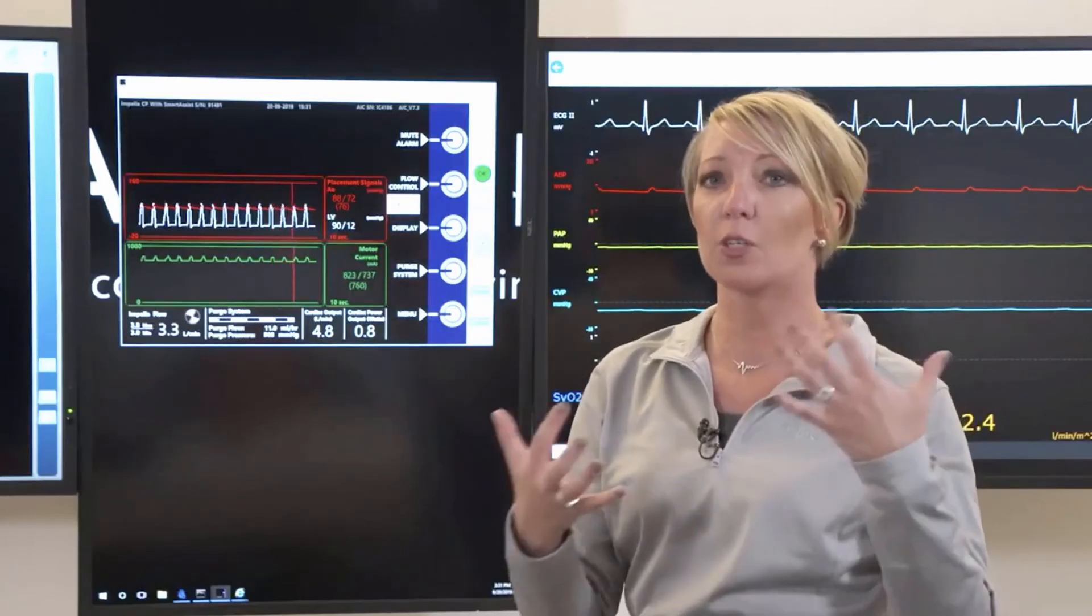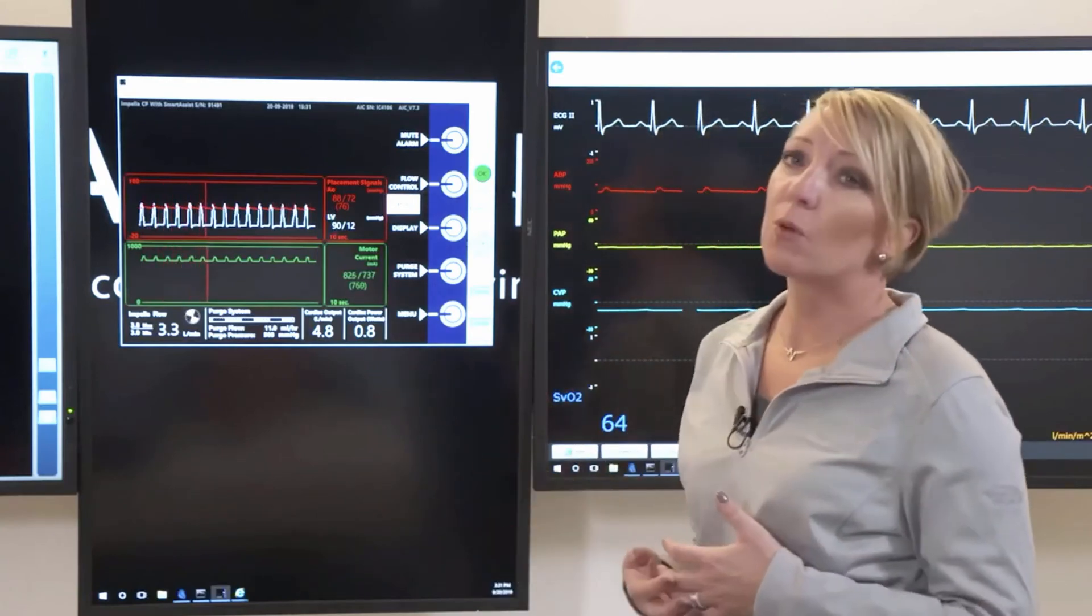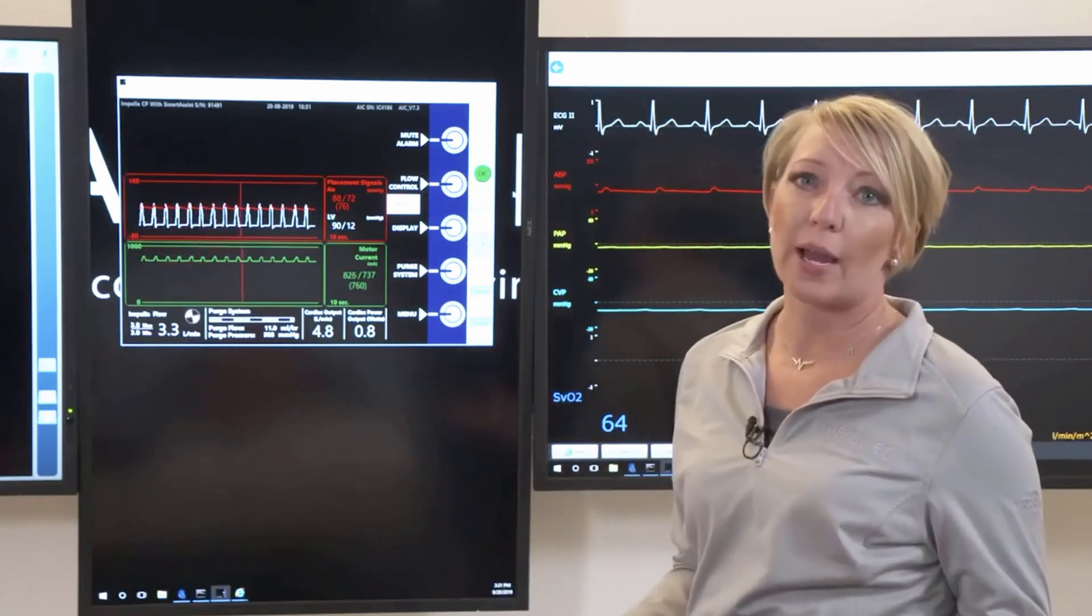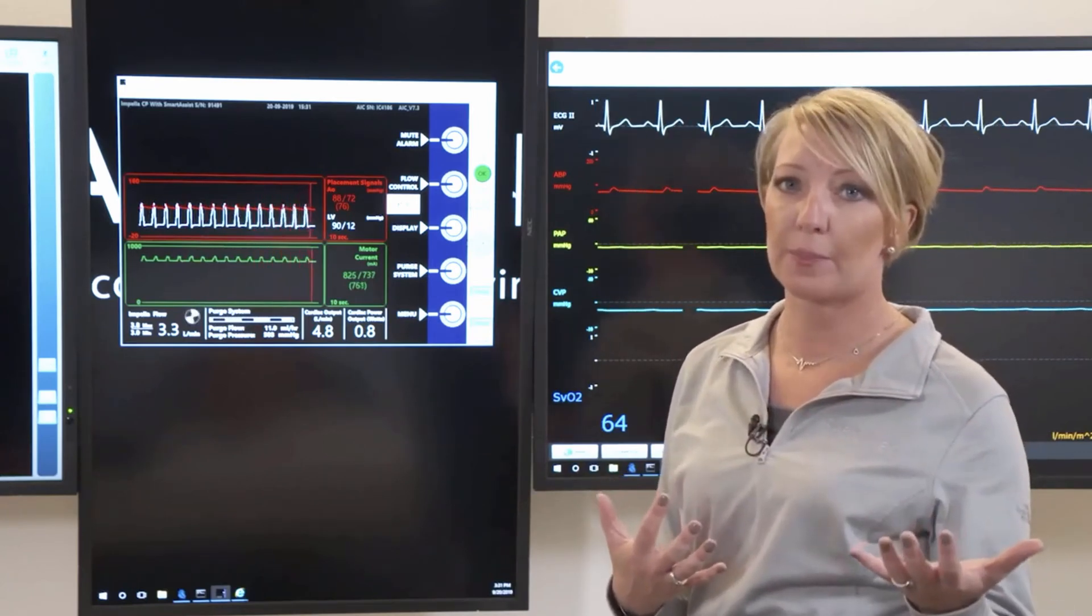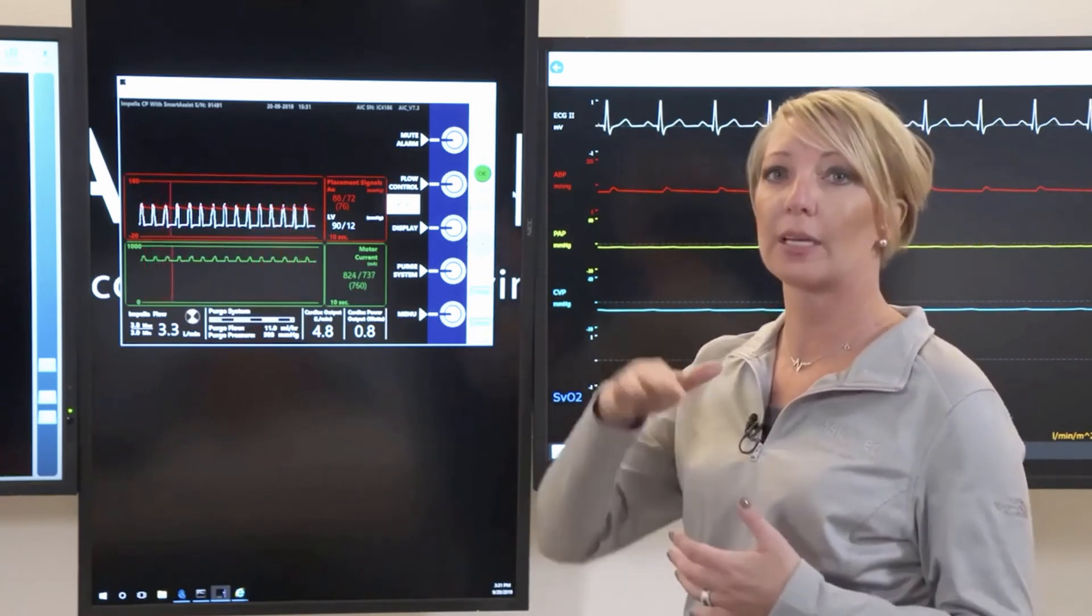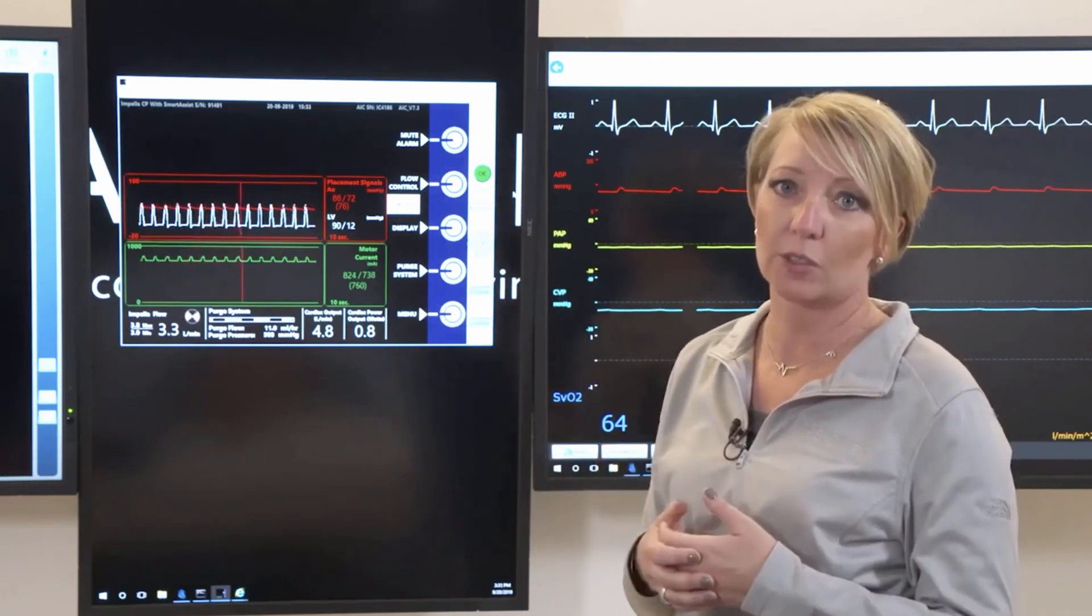You're still getting flow, it's just not at that ideal spot that you would have at that given P level. The white alarms are going to be more your FYI alarms. This is usually if they're doing something in the background with the purge solution. It might give you a message just saying hey, I did this. More of an informational alarm.